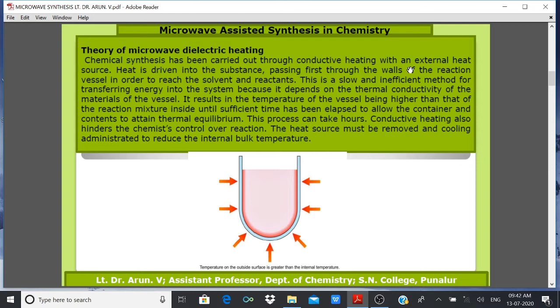It results in the temperature of the vessel being higher than that of the reaction mixture inside, until sufficient time has elapsed to allow the container and the content to attain thermal equilibrium. This process can take hours. Conductive heating also limits the chemist's control over the reaction. The heat source must be removed and cooling administered to reduce the internal bulk temperature.